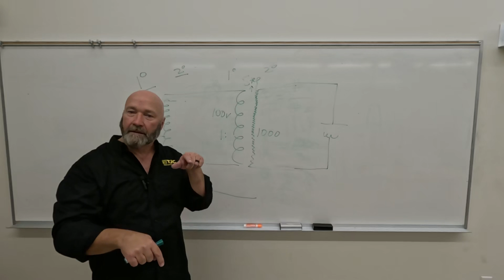So off of this is our filament circuit. And with a filament circuit, we've got an MA selector, and it is also a rheostat. Why we don't draw that one like this one, I have no idea. But it's going to be set to specific levels. Where with KVP, we can adjust KVP by 1 KVP, the MA selector, maybe that's why we draw it like that, has specific levels. It's preset to like 100, 200, maybe 300, 400, 500, and so on. Okay, so it's specific. And then what we want is we don't want our electrons to go from cathode to anode too early.